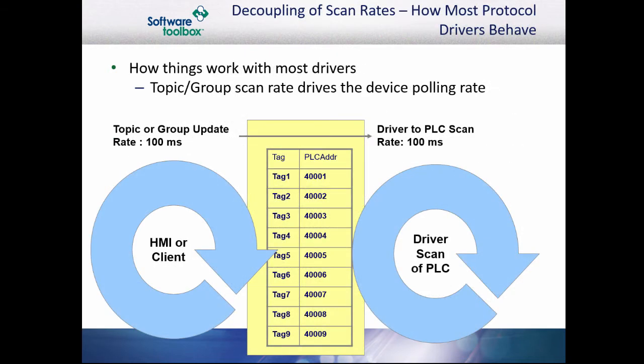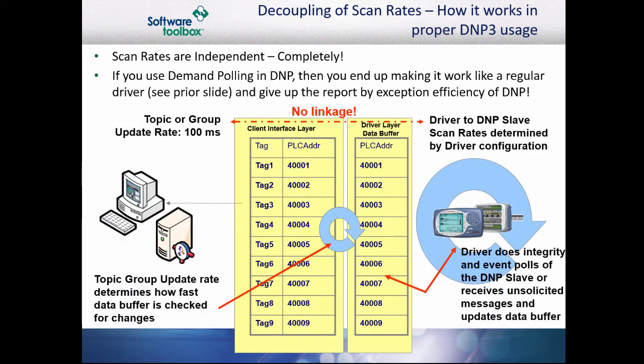DNP3 decouples the scan rates with proper usage. In most drivers, the topic or group scan rate in the HMI client drives the device polling rate. The client will send a request for data at a given update interval, and this is passed to the driver layer causing a scan of the devices at the same rate. With proper DNP3 usage, the scan rate between the client and server and DNP3 master and slave are completely independent. The client sends a data update request at one interval causing the client to pull the driver data buffer at this rate, while the driver is performing integrity and event polls at the rate specified in the driver, updating the buffer at these rates.